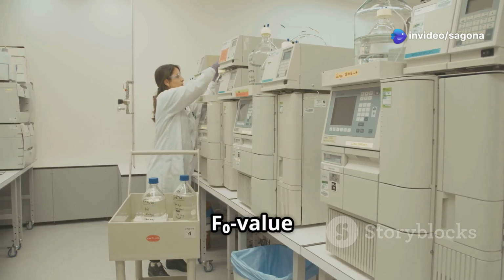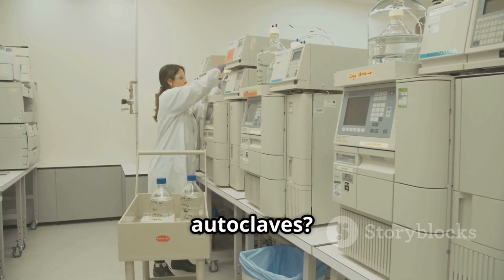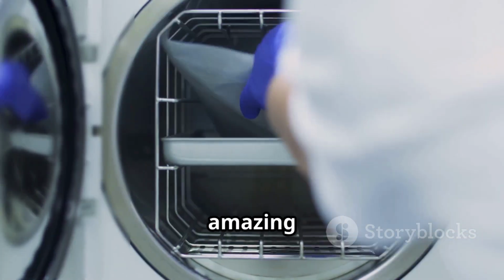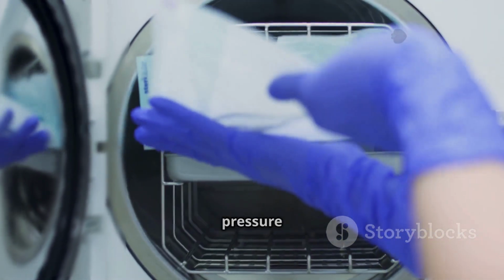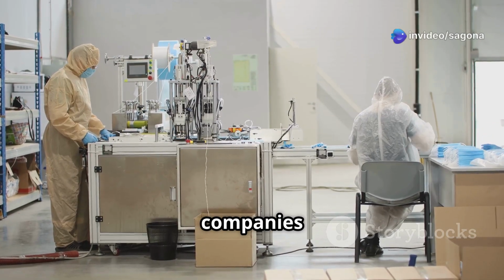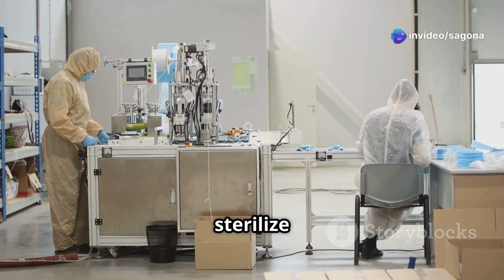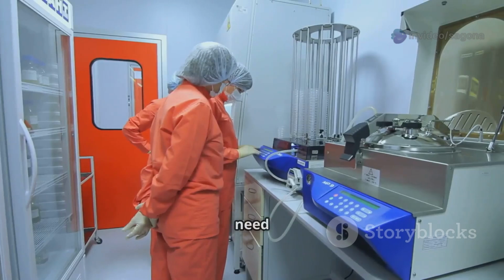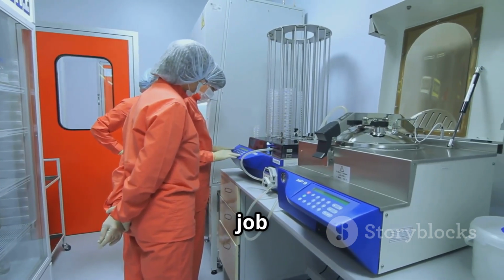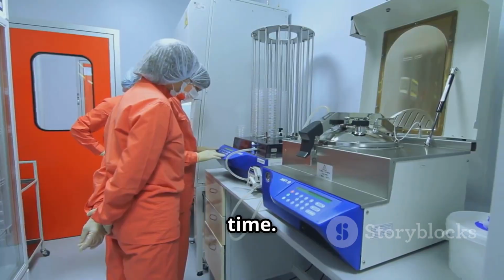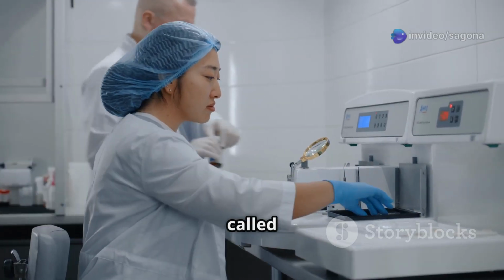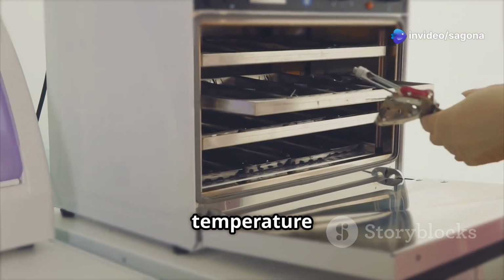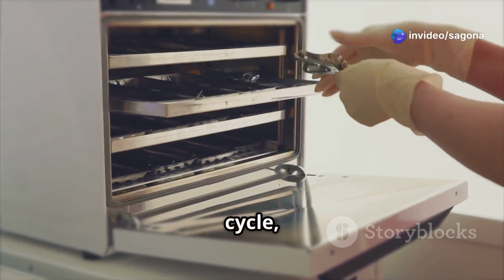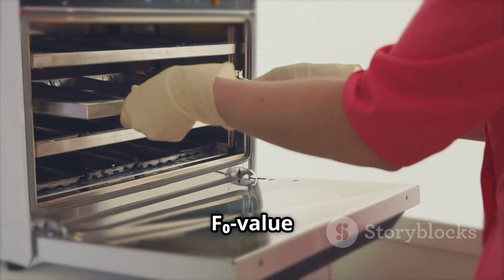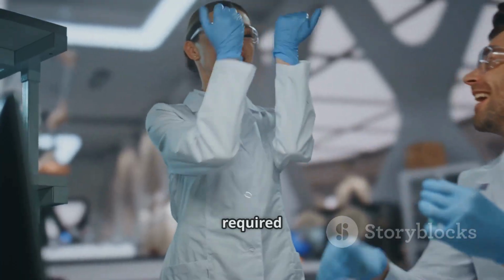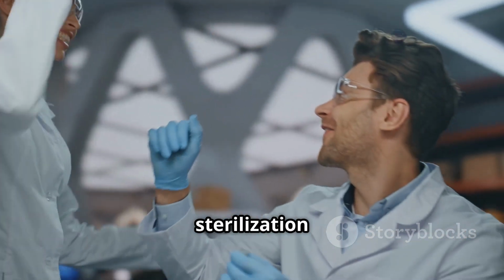Now, why is this F0 value so important, especially for things like autoclaves? Autoclaves are these amazing machines, a bit like super strong pressure cookers. Hospitals, labs and food companies use them all the time to sterilize equipment, media or products. But we need to be absolutely sure they are doing their job perfectly every single time. That's where F0 value helps with something called validation. By placing temperature sensors inside the autoclave during a cycle, scientists can calculate the F0 value achieved. If it meets the required target, they know the sterilization was successful.